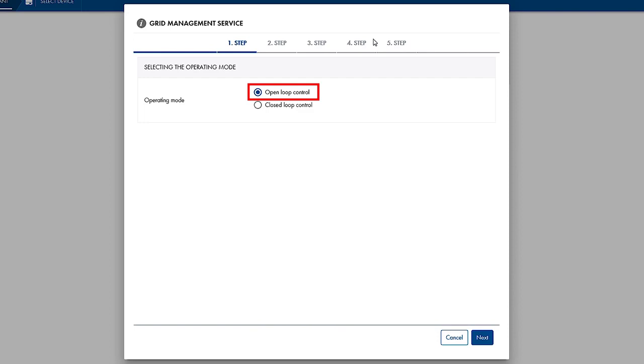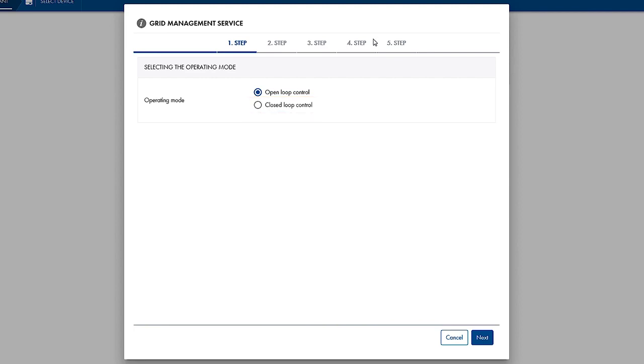In this case, the power set points apply only to the generation power of the PV system, and no measurement is necessary at the Grid Connection Point. The closed-loop control is used when the power set points apply at the Grid Connection Point. In this case, the power at the Grid Connection Point has to be measured. Data Manager M then uses the measured values to control the output power of the inverters, so that the defined feed-in power 0 to 100% at the Grid Connection Point is maintained.